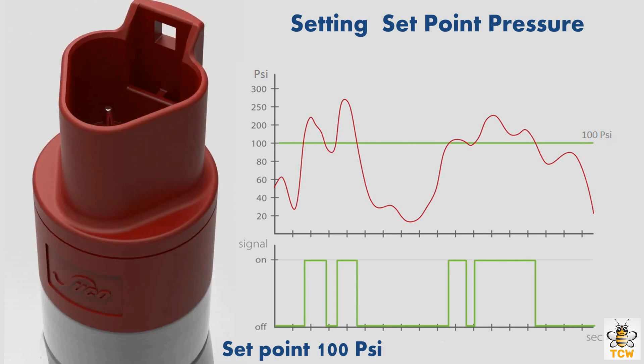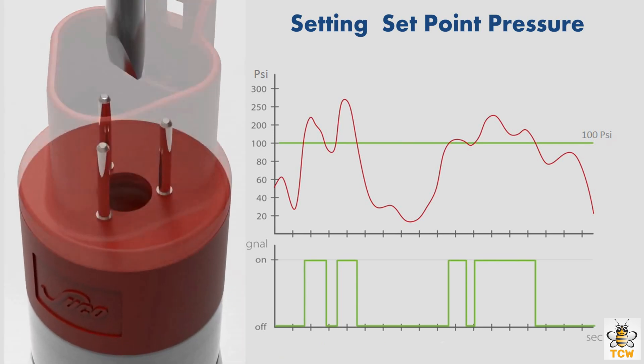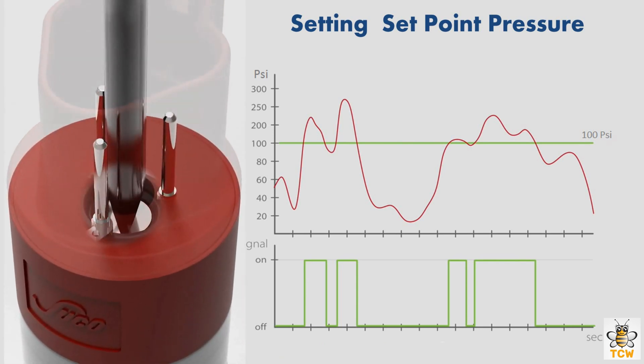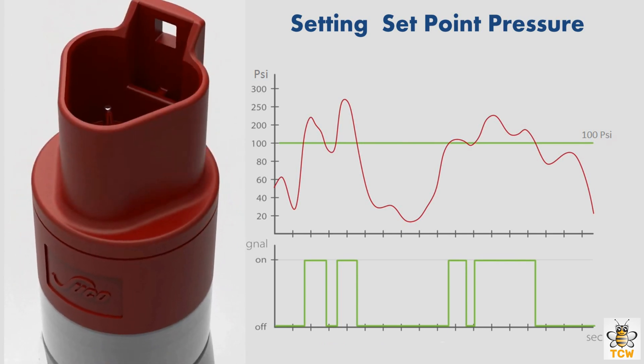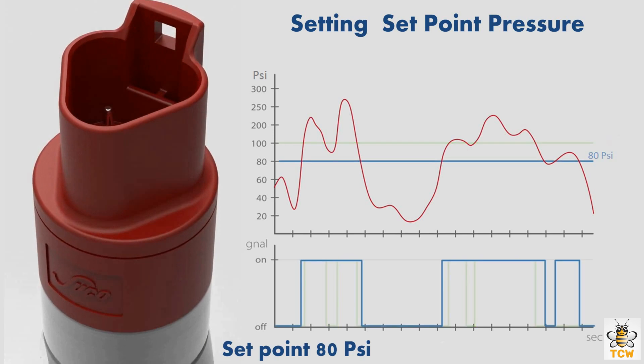On the right is the output signal chart of the pressure switch with a set point of 100 psi. We can see from the chart that the pressure switch signal is on if the pressure is above 100 psi. To change the set point pressure, turn the regulating screw until it reaches the new set point pressure. The new set point pressure is 80 psi, and we can see the change in the output signal chart — the pressure switch signal is now on if the pressure is above 80 psi.